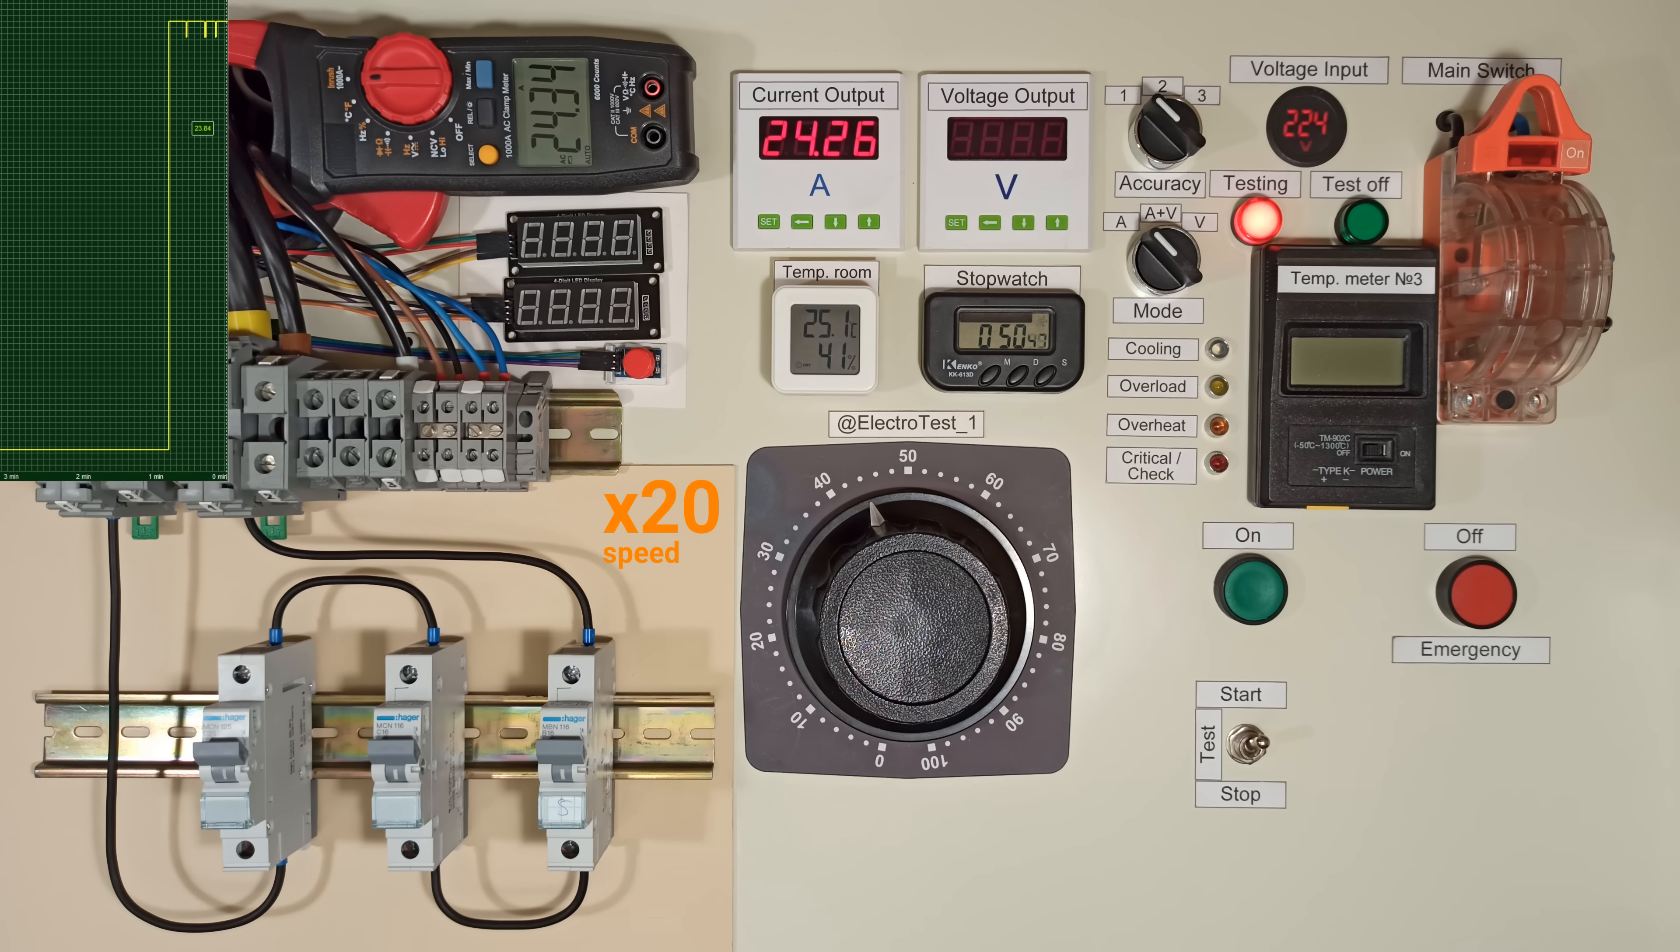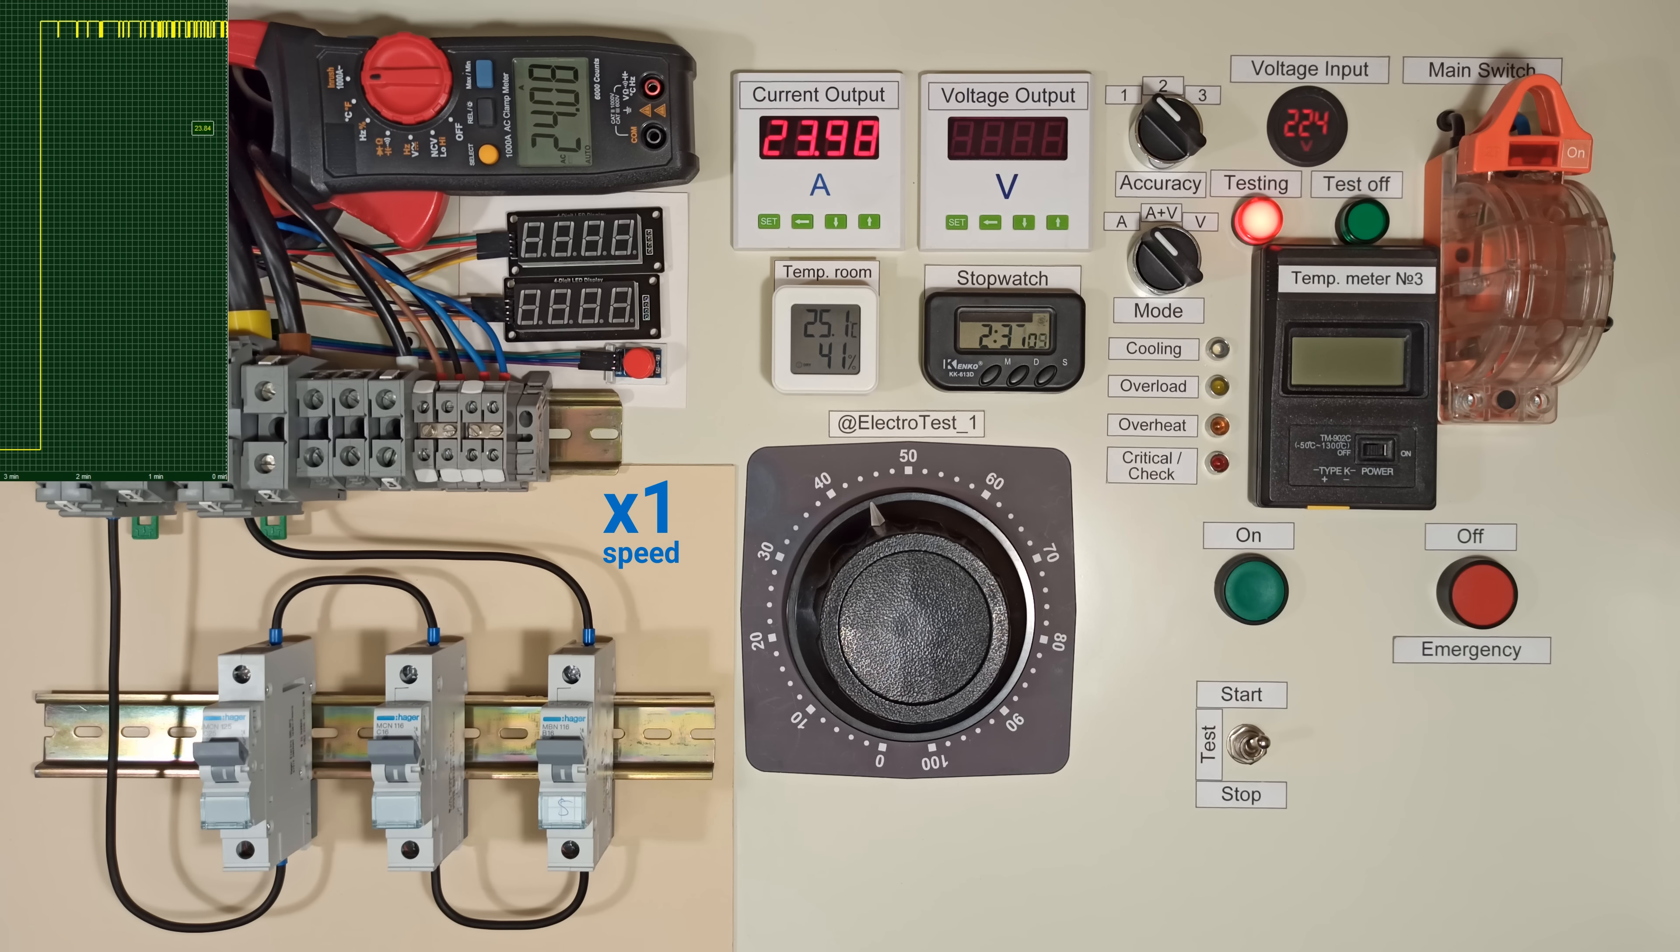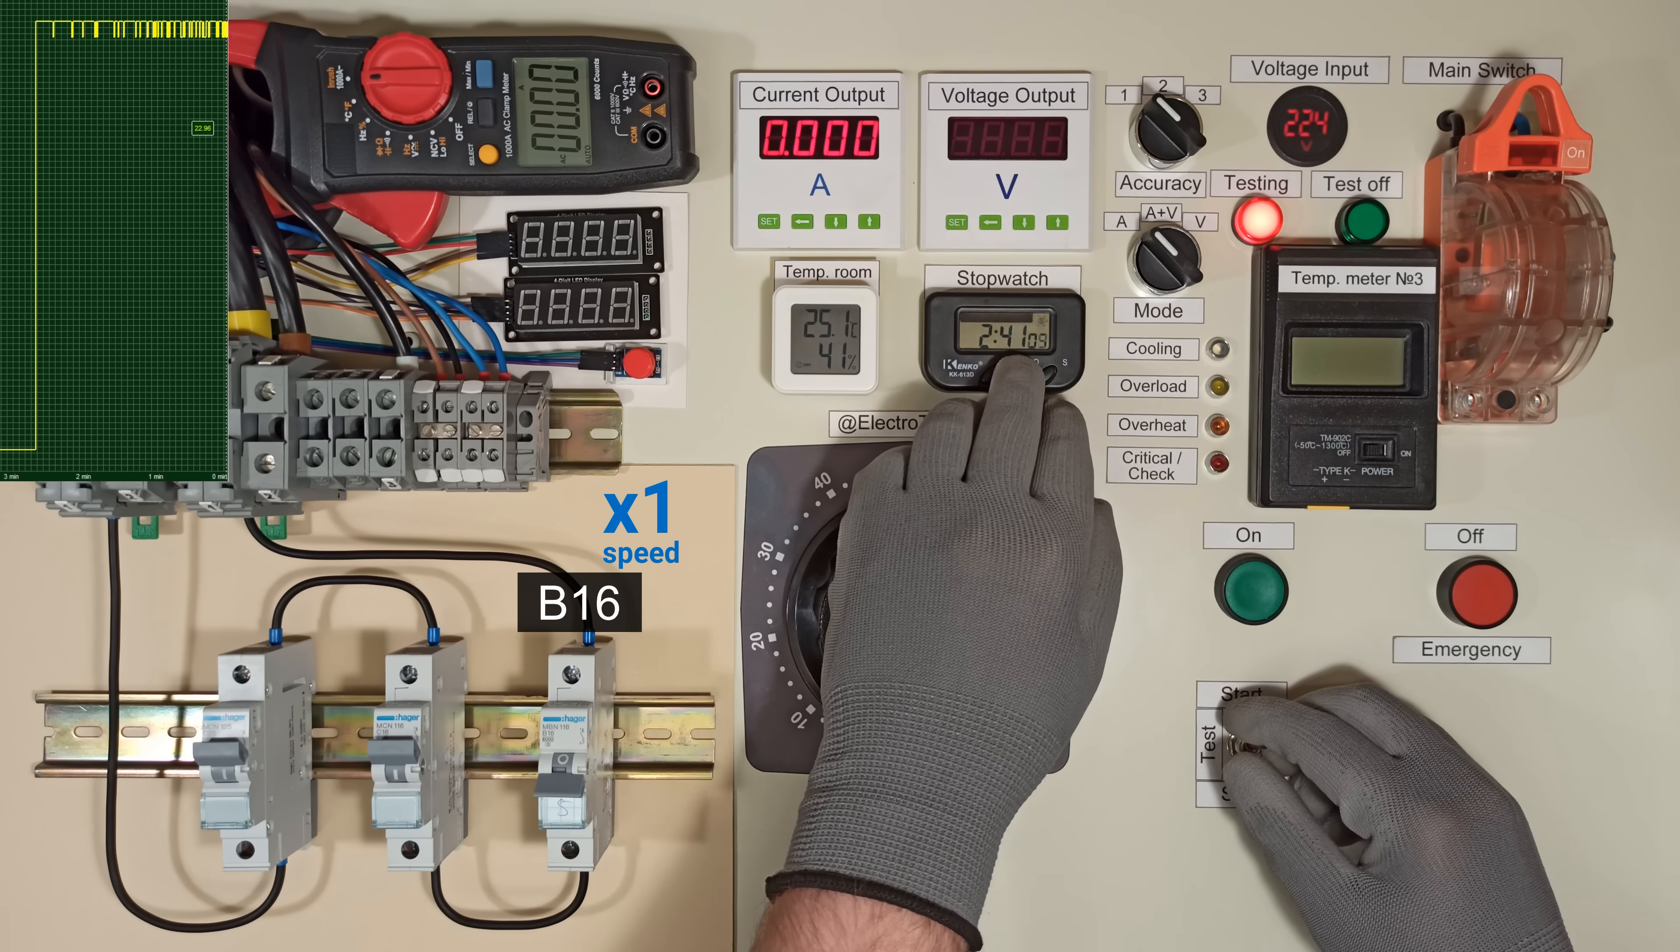At times 1.45 the trip time is the longest, and theoretically there is a large time variation. The B16 tripped first.